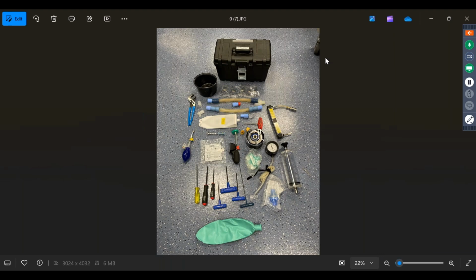So doctor, did you check the cuff? Did you check the cuff? Oh, the cuff is fine. I'll say, let's test it with my cuff pressure gauge. And sure enough, one of the calls that really sucked for me was like one of the big professors who was a major chair of the department. And I'm going, you know, it's got to be the cuff leaking because it can't be the machine because we've tested everything. And I'm in there, let's measure the cuff pressure. And he says, well, it can't be the cuff. And then his resident walks in and looks around and she just goes up and pumps some air into the cuff, and the leak goes away. And he's like looking at me. But anyways, cuff leaks.